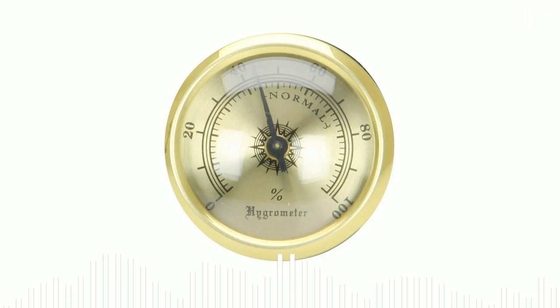The difference between dry and wet bulb readings depends on how much vapor is already in the air, in other words, on humidity. The lower the humidity, the higher this difference will be. Difference values for different dry bulb temperatures are available in a special psychrometric table, which can be easily found on the internet. Determine the humidity values from it.